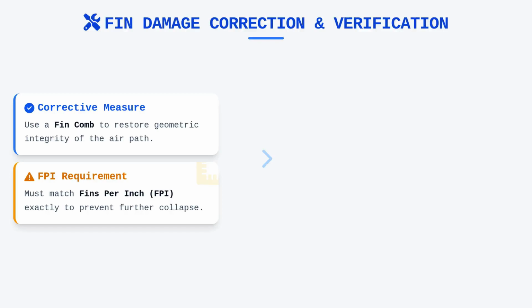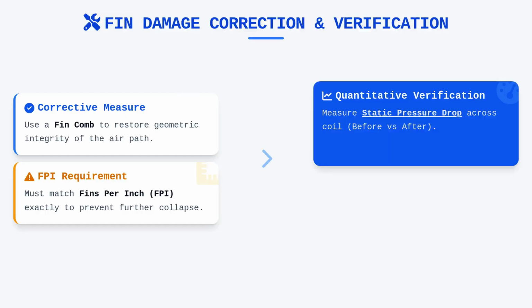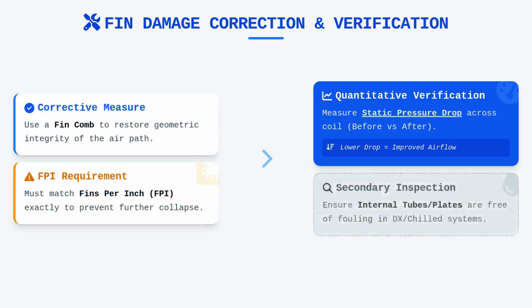After manual inspection confirms the removal of obstructions, you should perform quantitative verification of your work. This is most accurately achieved by measuring the static pressure drop across the coil before and after the cleaning procedure. A significant reduction in pressure drop while maintaining the same fan speed is the definitive indicator of improved airflow and successful debris removal. If the coil is part of a chilled water or DX system, you must likewise ensure that the secondary side, the heat exchanger tubes or plates, is free of internal fouling that could impede heat exchange.